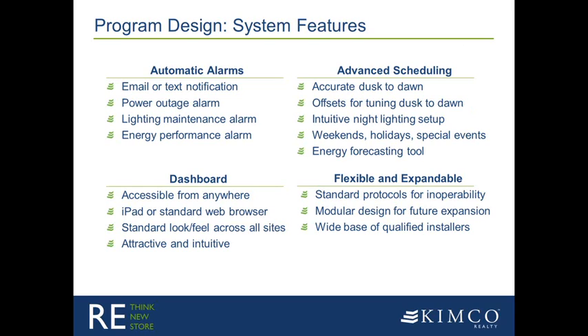We're also able to offset the on-off times based on dusk and dawn calculations, and provide an intuitive way of setting up night lighting schedules for certain circuits to stage off at night — you'll see that a significant portion of the savings is driven by that feature. Property managers can also enter custom schedules, and there's a tool that gives them estimated energy savings in real time as they make scheduling adjustments. That immediate feedback we found to be very important in motivating them to optimize the site's performance. The dashboard on the lower right is for the property manager to get the most out of the system.